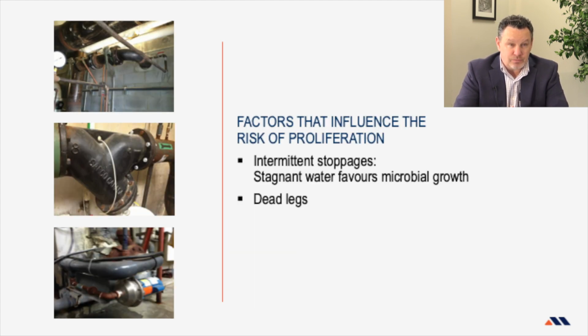Other factors that we need to manage are dead legs or intermittent operations. Bacteria, generally speaking, like stagnant water. They have a lot of time to grow, especially if they see some nutrients lying around in the water, or other bacteria, dead bacteria, or some organics, oils and things like that. Intermittent operation and dead legs are beautiful places for bacteria to grow. And what they do is they create very high concentrations of bacteria in the rest of the system, which just helps bacteria and Legionella grow.